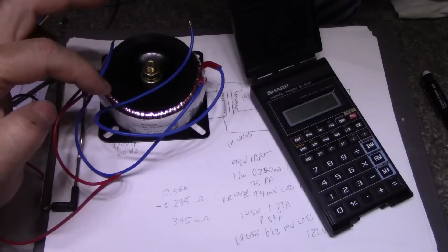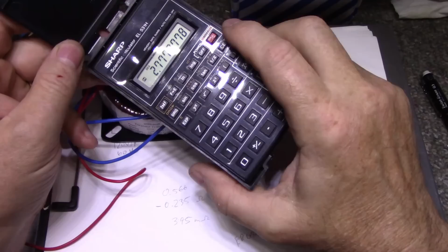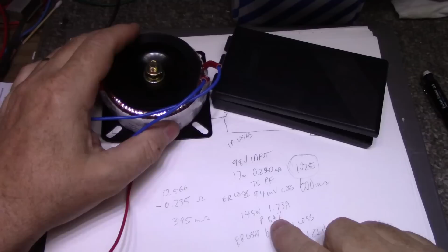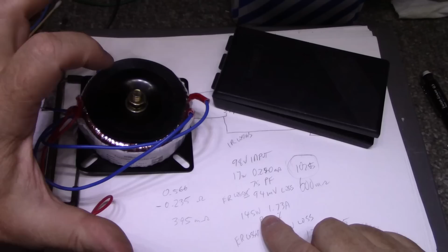In case you were wondering, this secondary should be good for several amps. We have a 50 volt amp transformer and it's delivering 18 volts, so if you just do the simple resistive load, 50 divided by 18 comes back with 2.77 amps at full load on a resistive, non-reactive load. We're still well within our limit here. We're asking for 1.73 amps, and this thing will deliver 2.7 amps, so this is rated, I think, correctly rated.